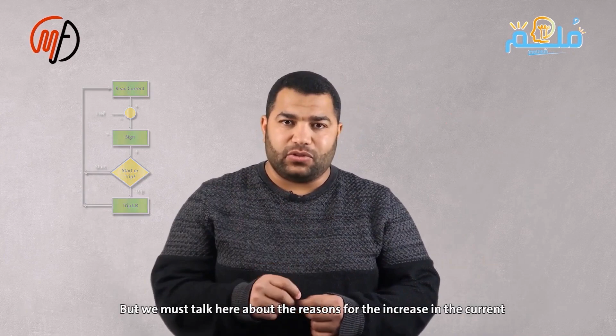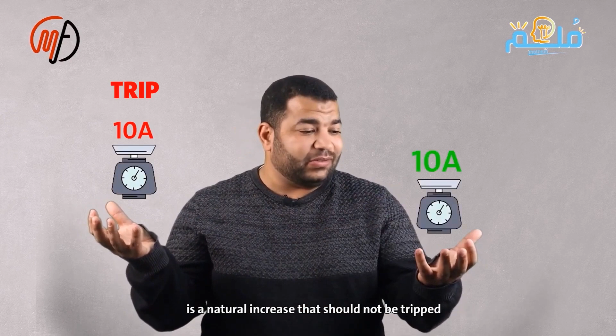We must discuss the reasons for current increase. Is any current increase a fault causing disconnection? No. This is the relay challenge. How can the relay tell if 10 amps is a fault causing disconnection or a natural increase not causing disconnection? Moreover, the relay must tell if 0.1 amps is a fault causing disconnection or a natural increase.